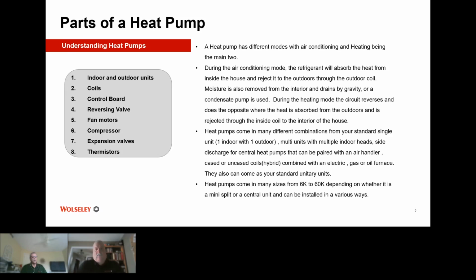Now, the parts of a heat pump. You have an indoor and an outdoor unit. You have a coil in the outdoor and indoor units where the heat is absorbed by the refrigerant and then rejected, depending on what mode is selected. Control board, which is with the inverter, which is the brains of the operation. The inverter controls the speed of the compressor, which depends on the demand of the room or the system at that time. Reversing valve does exactly as it sounds, reverses the flow of refrigerant when the mode is changed from AC to heating or vice versa.